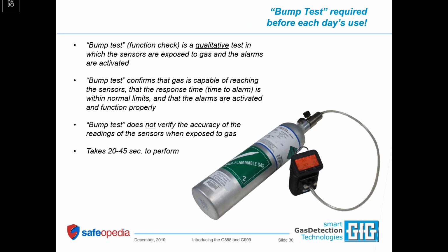Some of the big changes go beyond just requiring a monitor and using it. It defines how you are required to perform a bump test before each day's use, and takes you through the zeroing and calibration procedures and steps. So the days when you could ignore calibration and bump testing are a thing of the past.